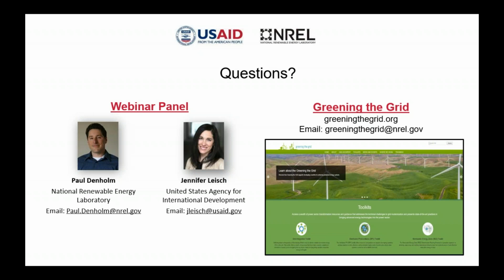Adding storage at the end of a congested transmission line, you can ship energy during off-peak periods when the line isn't overloaded, then discharge storage when the line nears capacity. We've seen locations in the U.S. where storage relieves congestion, typically not on really big lines—utilities are dipping their toe in the water, usually on long radial feeders or lower voltage circuits. As storage gets cheaper, I think we'll see it applied on larger transmission systems, deferring tens or even hundreds of megawatts of capacity instead of just one or two.